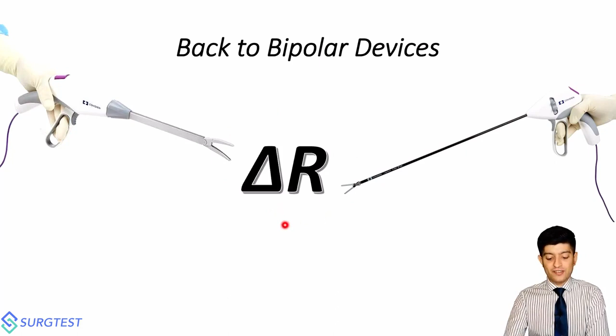So when we talk about dedicated vessel sealing devices, there is a pretty complex computational algorithm which is utilized to figure out when exactly an effective vessel seal has formed. This is in stark contrast to the plain Jane bipolar forceps that we use in surgery, where I could keep the bipolar pedal pressed all day and it will keep firing energy across the tissues, not caring whether a seal has formed or whether tissues are getting excessively charred. These devices, because they are checking this change in resistance, have several inbuilt safety mechanisms.